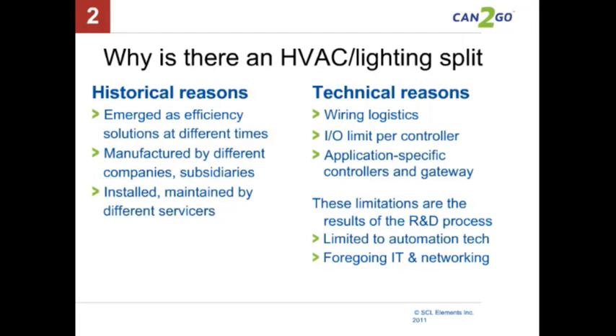Then there are technical reasons: there's always the logistics of wiring, and always the limit of I/Os, the inputs and outputs available per controller. So imagine in a particular zone, if you have to control all of the lighting points and all of your HVAC control points, your controller will max out on its I/O limit. So that might be some reason to have two separate systems.